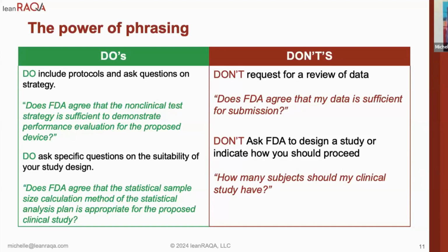And they're insistent on turning that in their pre-submission, and FDA shuts that down very quickly, and they will not look at data. So even if you're going to do OUS studies or testing, I would still submit the protocols in advance to make sure you can get the most mileage and reuse out of data that you may obtain prior to going into your FDA submission.